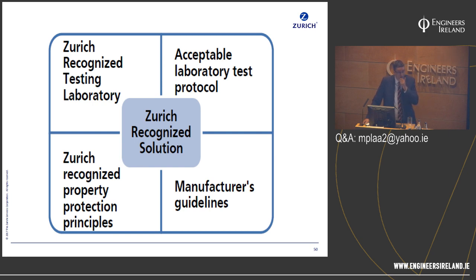Am I correct in assuming that the warehouse you came across with the water mist, you're no longer on cover? I don't know whether we're on cover or not, but I did make an assessment to the underwriter that the system was ineffective and wouldn't be suitable for such a challenging, effectively high hazard fire load. And to complicate it further, it had high bay racking to 10 meters, so that clearly was a roof and rack domain, with roughly 7.5 to 10 millimeters density at roof, and in-rack sprinkler protection every 2.5 to 3 meters.